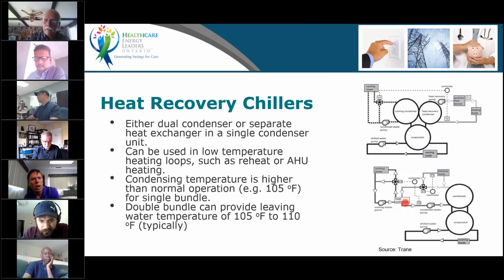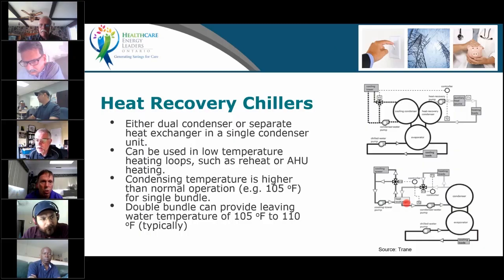A double bundle chiller typically will be able to achieve higher condensing temperature. So your heating loop is still a low temperature loop. That's the one thing you have to know about heat recovery chillers. They usually work with a low temperature loop, not a high temperature loop. If you have a high temperature loop and somehow you still want to do heat recovery, you would have to have a heat pump to boost that temperature up. That's not very common. Usually it's on the low temperature loop.